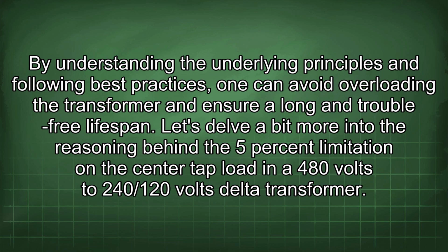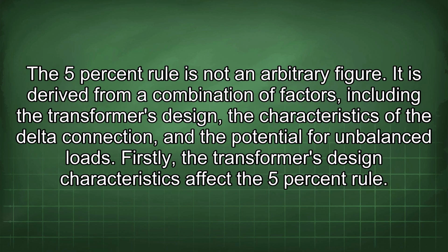Let's delve a bit more into the reasoning behind the 5% limitation on center tap load in a 480 volts to 240/120 volts delta transformer. The 5% rule is not an arbitrary figure. It is derived from a combination of factors, including the transformer's design, the characteristics of the delta connection, and the potential for unbalanced load. Firstly, the transformer's design characteristics affect the 5% rule.